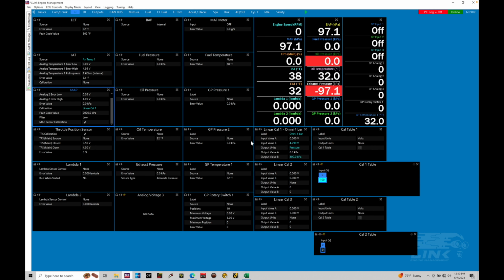If I click OK here, we're going to find that we're good to go. Now, let's take a look at a couple things. We're going to find here that we have an analog 2 low error and a high error. This is where we're going to have a little bit of a snag with this map pressure sensor. We're going to find the minimum voltage according to the data sheet is 0 volt. We're going to say in this case that our low error has to be set here to 0.